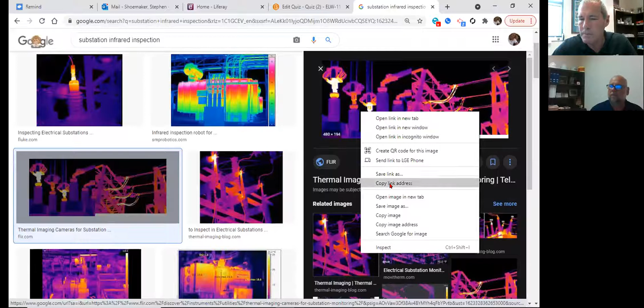This is an infrared shot of a substation and the connections inside it. Notice the center bushing on this large transformer — it's doing a pretty decent job emitting heat. That heat is produced by resistance, from a connection that isn't clean or tight. Look what's happening over here — all that heat is being produced and just dissipates off.